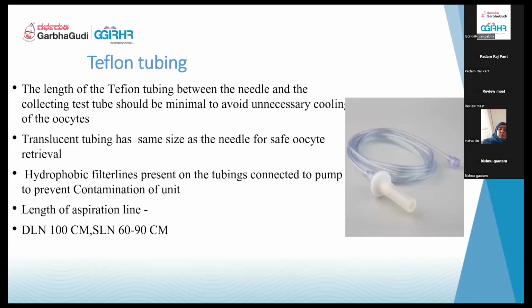This is the tubing that is used for suction pressure. What is the material that the tubing is made of? It is Teflon tubing. The distance between the needle and the collection test tube should be minimal to avoid unnecessary cooling of the oocytes. These are translucent tubes, with the same size as the needle, for safe oocyte retrieval. The hydrophobic filter lines present on the tubings connected to the pump prevent contamination of the unit. The length of these aspiration needles is about 62, tubings are 60 to 90, and 100 centimeters in double lumen.